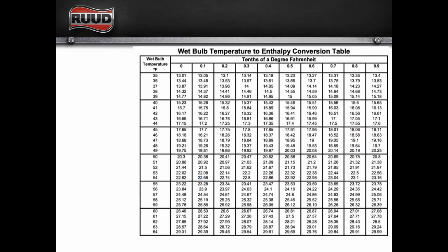So what we're going to do is we're going to look at the table. And so on this table, our wet bulb temperature is the column all the way over on the left-hand side, right? It starts at 35 degrees and goes down to, I can't see all of it, probably 63, 64. I've got a bar at the bottom of my screen. And then across the top where it says tenths of a degree Fahrenheit, if we had measured, say, 35.5, our enthalpy would be 13.23. It's important to note those tenths of a degree because that will change your formula a little bit. You want to put in the numbers as accurately as you can, right?